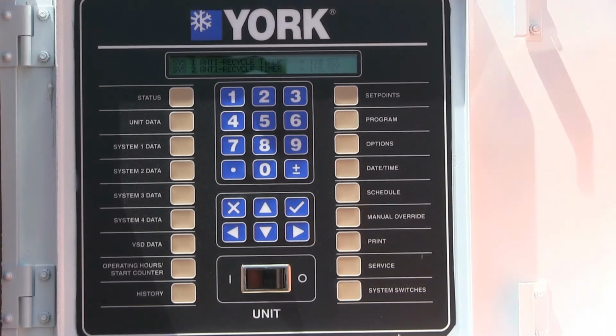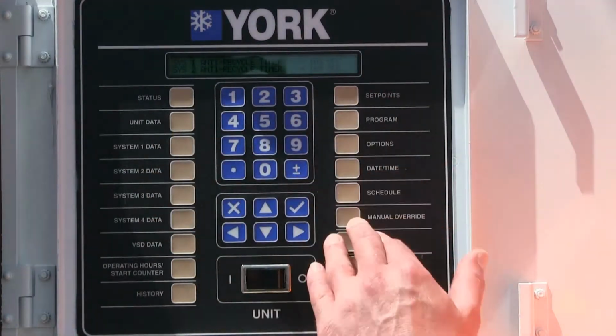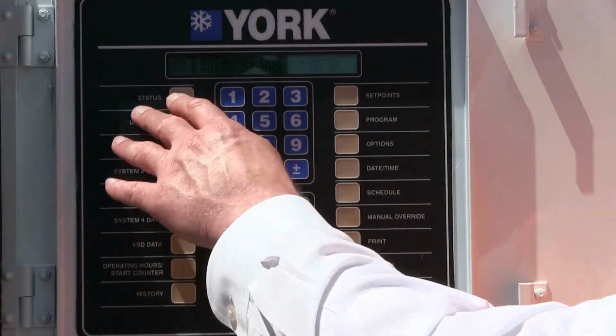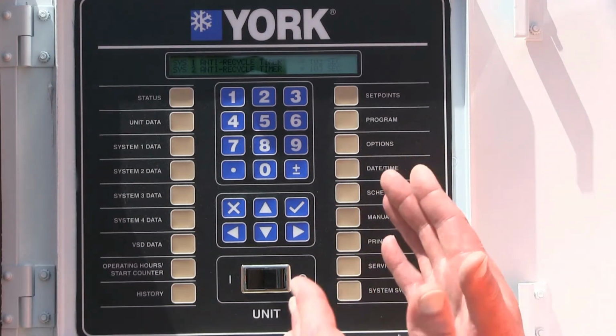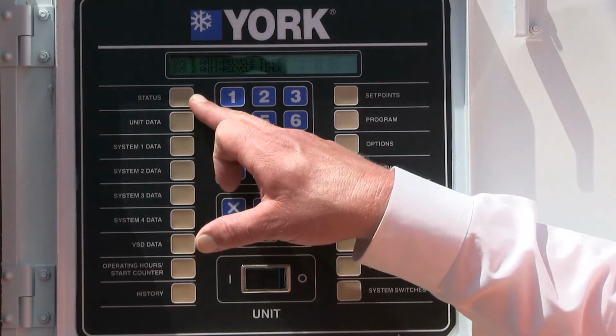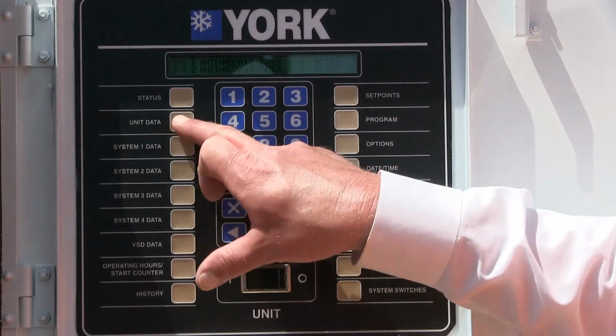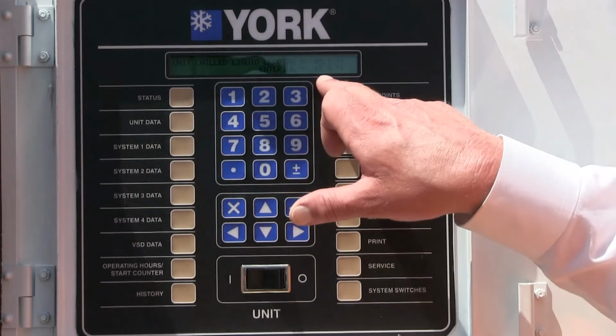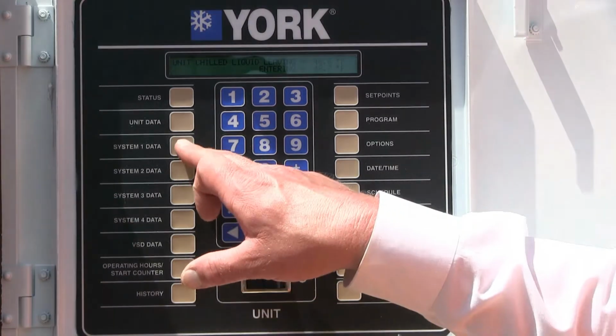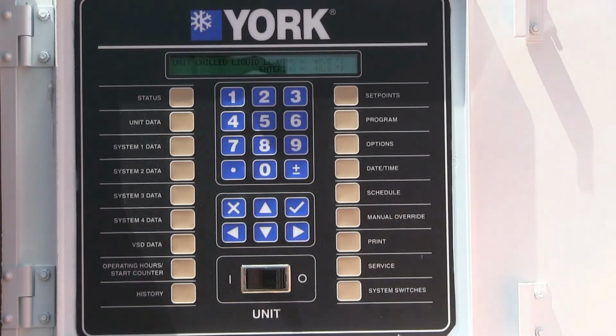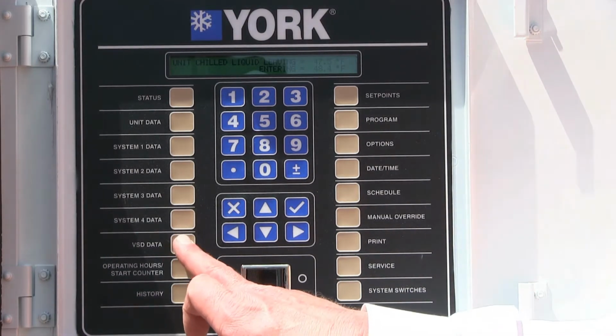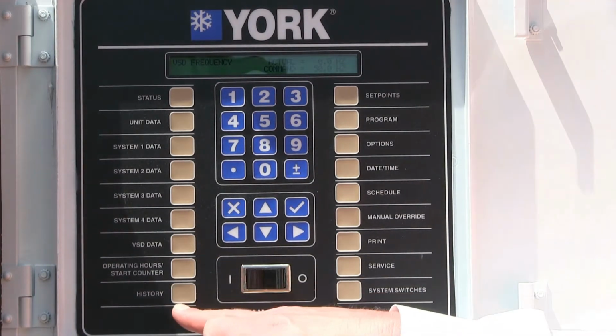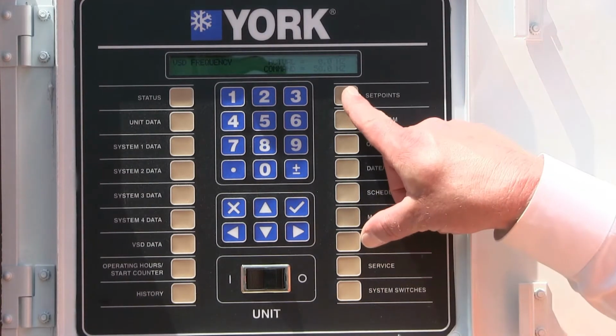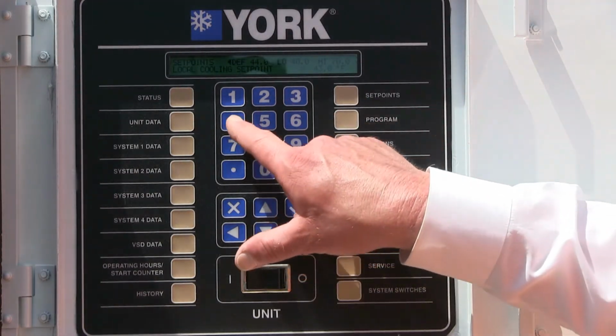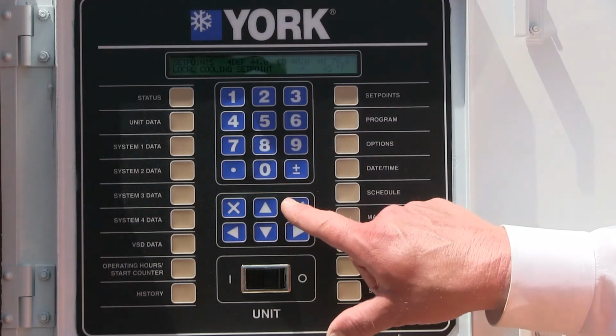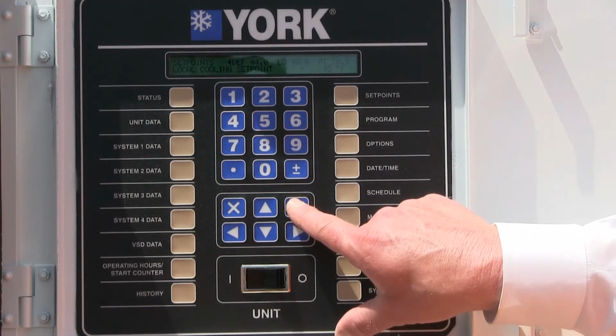So just to recap the keypad, again, there's nothing you can do to push on here that's going to hurt anything. So always go back to your status. The buttons that you're going to be primarily familiar with is your status, which is your home, tells you what the machine's doing. Unit data is where you'll find the chilled water entering and leaving temperature. The data for system 1 and 2 is, again, the technical data of the refrigeration system. VSD is your variable speed drive data. Operating hours and history, we covered that. Set point, a very important one, you're going to push that. Type in whatever set point, and the standard set point is 45 degrees. That's what we've designed all of our equipment to.